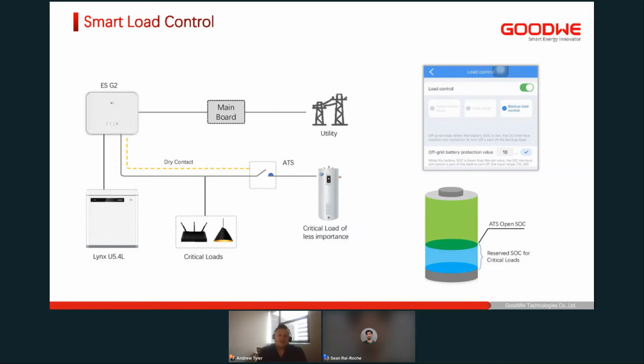Then a similar example, but we're talking about having a specific load on the backup circuit. Typically, when you have a load on your critical load or backup output, it would drain the batteries, but maybe it's important for you to have this type of load still connected to the backup, but with the ability to control it based on our smart load control. So same concept, a dry contact to an ATS, except the load is on the backup side. So you can still use your normal critical loads with only this critical load of less importance, or your hot water tank rather, can still switch on or off on the backup circuit based on how you've set it up via our software.